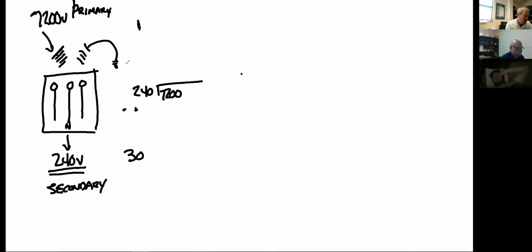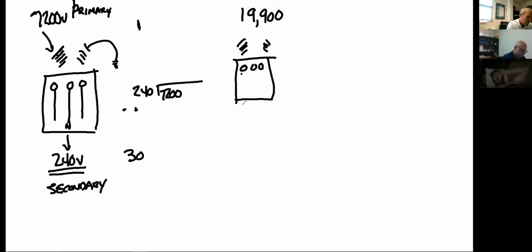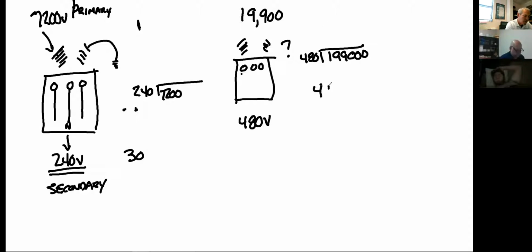Let's try another one—I'll use one of your voltages, Professor V. Primary of 19,900... let's say 480 volts, that's my output on secondary. What's the ratio? Get those phones out, burn up those calculators. Is it 4.5 to 1? No, 41.5 to 1. That's the ratio of that transformer.